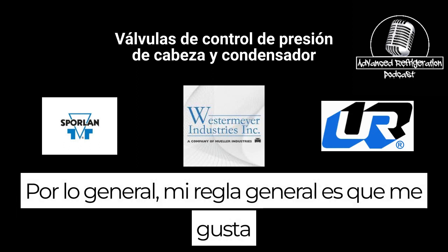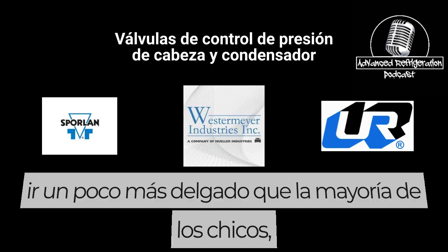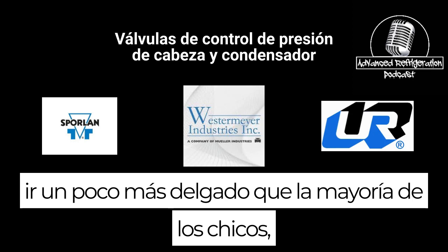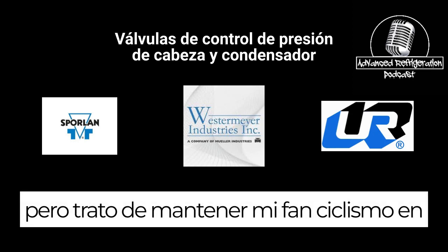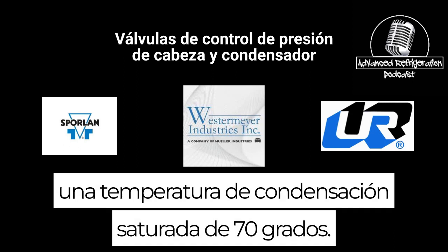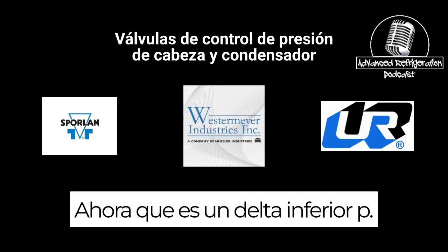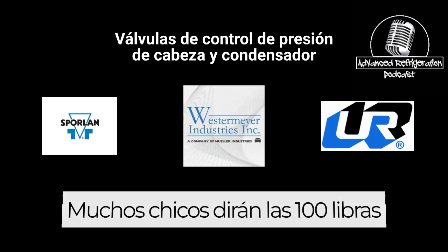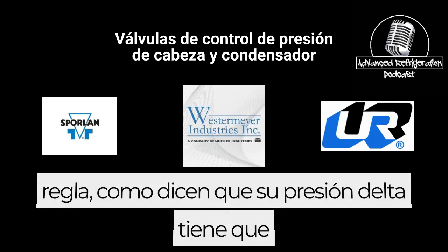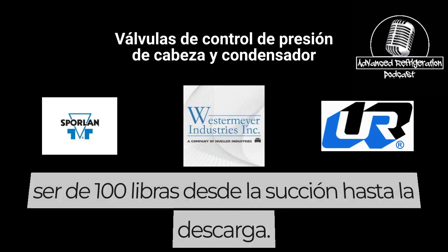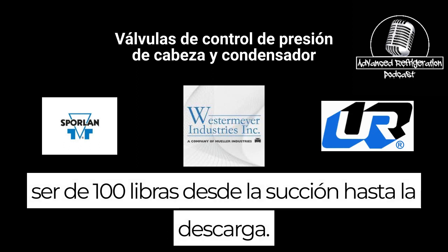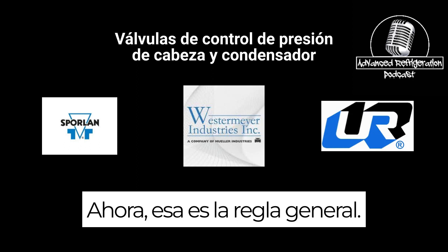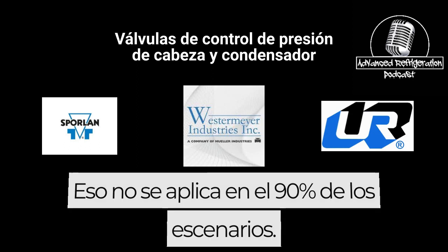Generally, my rule of thumb is I like to go a little more lean than most guys. I try to maintain my fan cycling at a 70 degree saturated condensing temperature. Now, that is a lower delta P. A lot of guys will say the 100-pound rule, that your delta pressure has to be 100 pounds from suction to discharge. Now, that is a rule of thumb. That doesn't apply in 90% of scenarios.